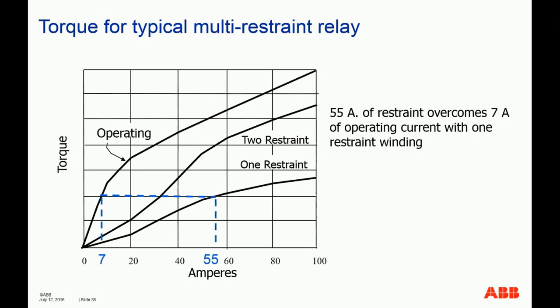Here, it's actually talking about the same thing. For the 55 amp of restraint, it overcomes 7 amp of operating current. So basically, if during an external fault, CT saturation or something causes 7 amp of operating current, as long as you have at least 55 amp of restraint current, you would overcome that, so you won't misoperate.